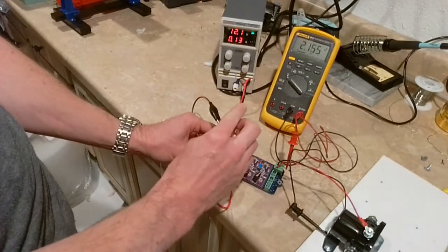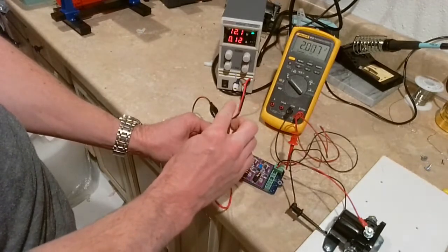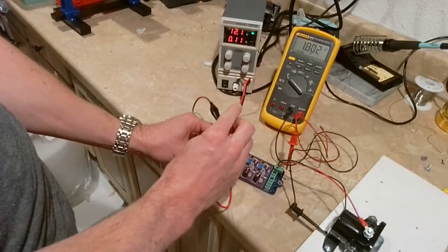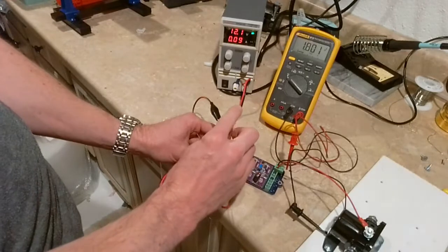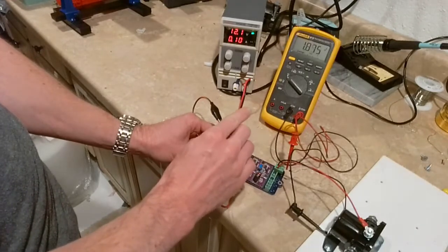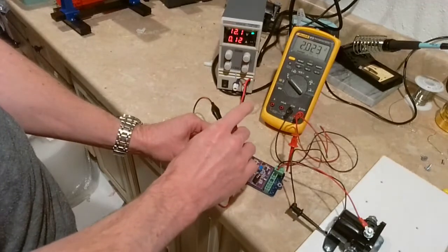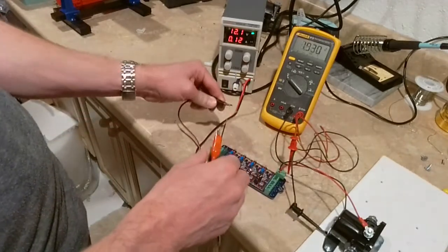Or you can decrease it all the way down until the solenoid drops out. You can see it usually happens around 1.5 volts. Yeah, there you go, so it dropped out right there. And so we know that that's about as low as we can go. Turn it up a little higher than that.